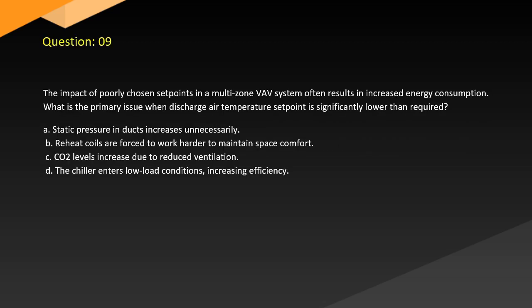Question 9. The impact of poorly chosen set points in a multi-zone VAV system often results in increased energy consumption. What is the primary issue when the discharge air temperature set point is significantly lower than required? A. Static pressure in ducts increases unnecessarily. B. Reheat coils are forced to work harder to maintain space comfort. C. CO2 levels increase due to reduced ventilation. D. The chiller enters low load conditions, increasing efficiency.